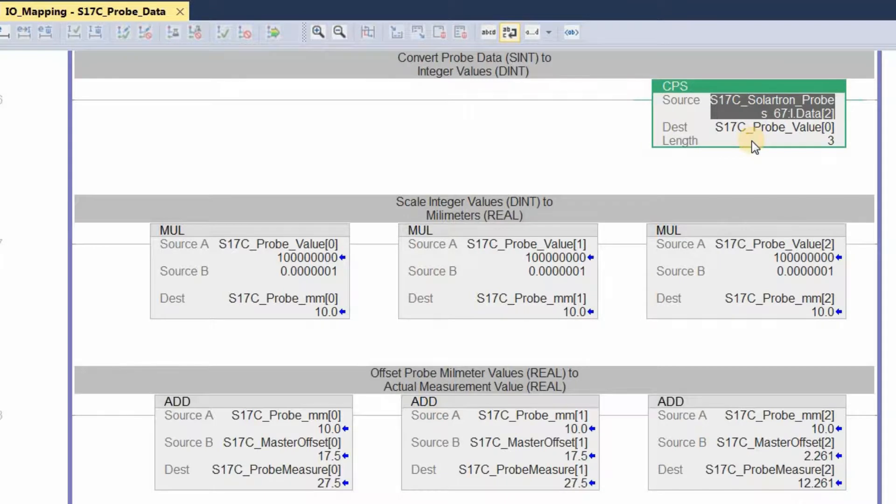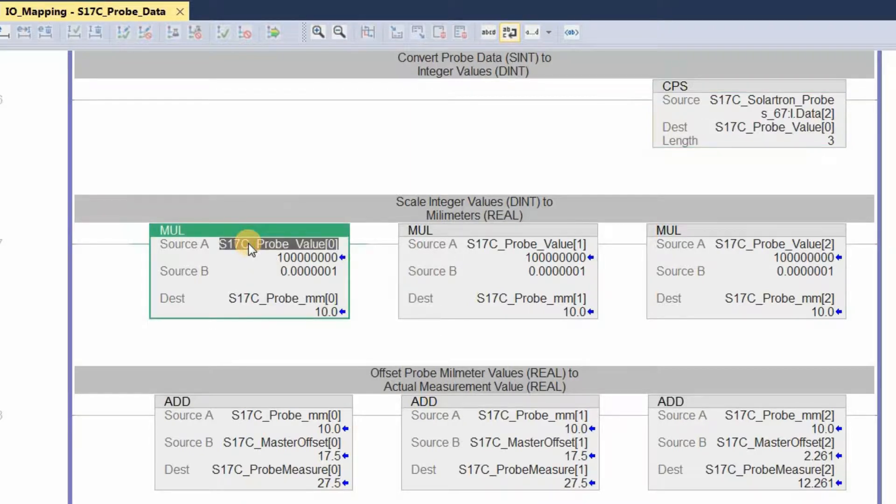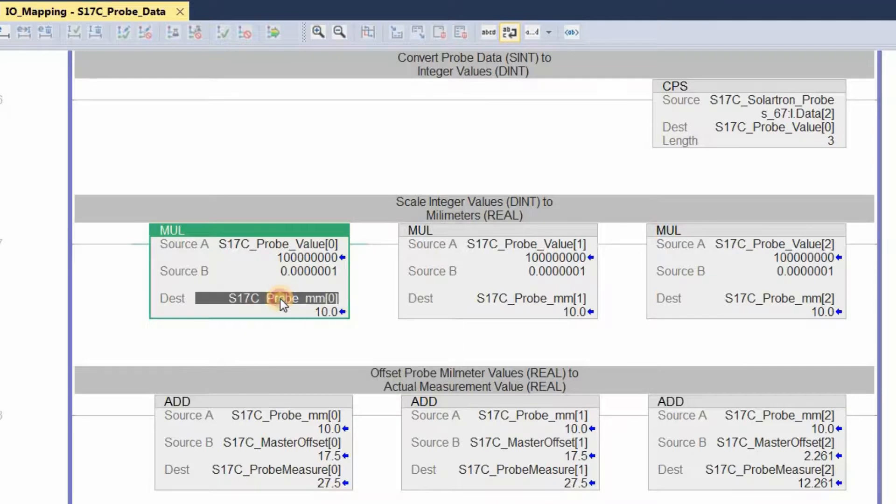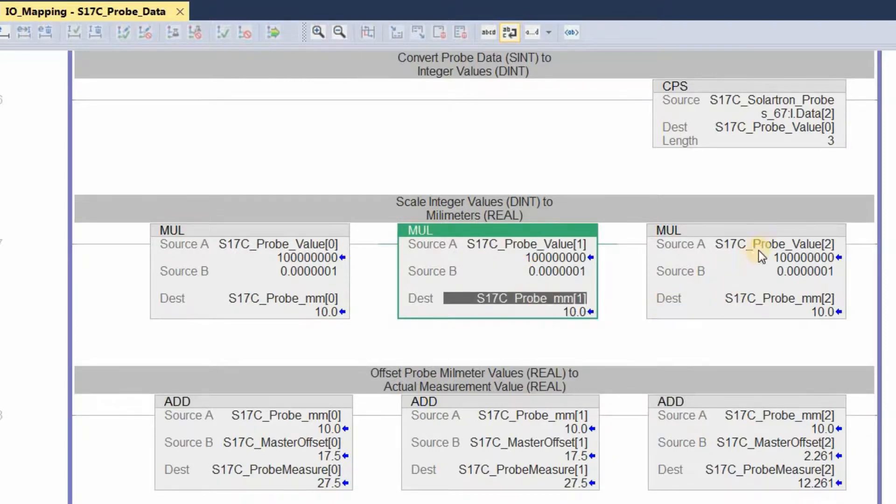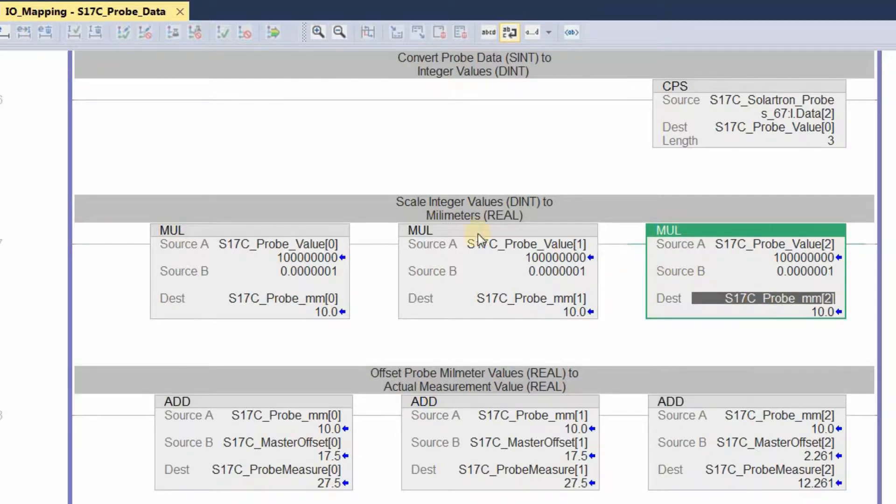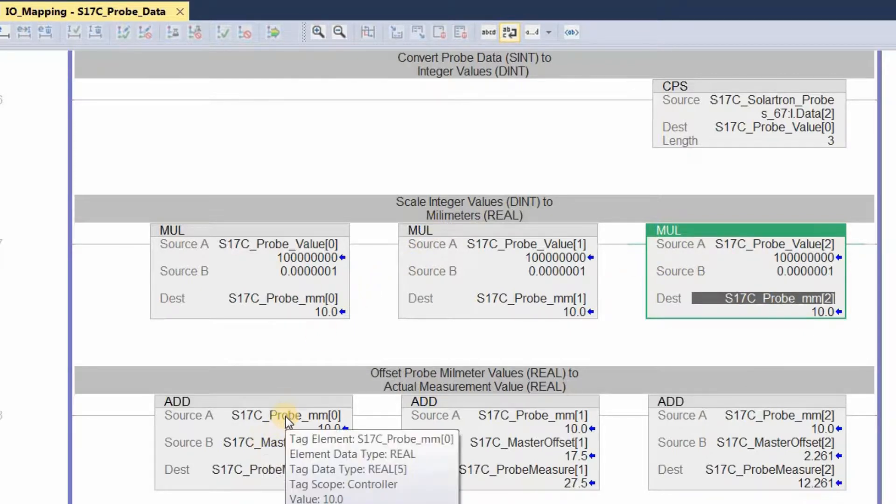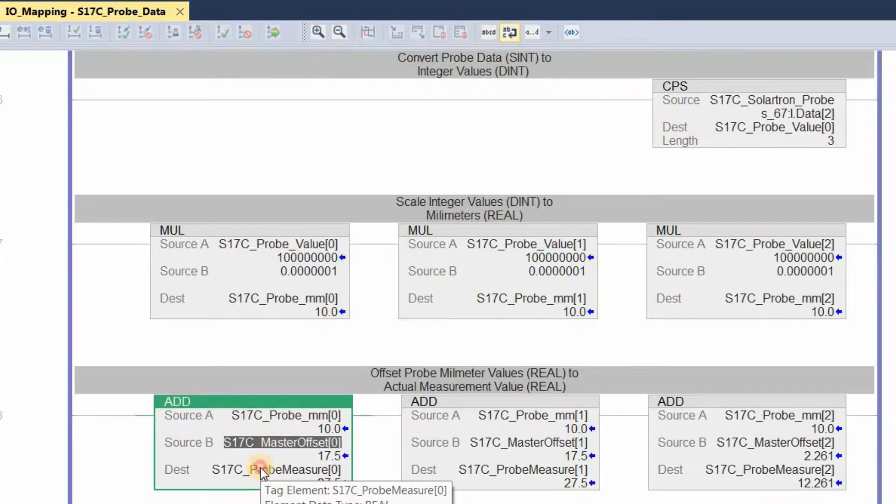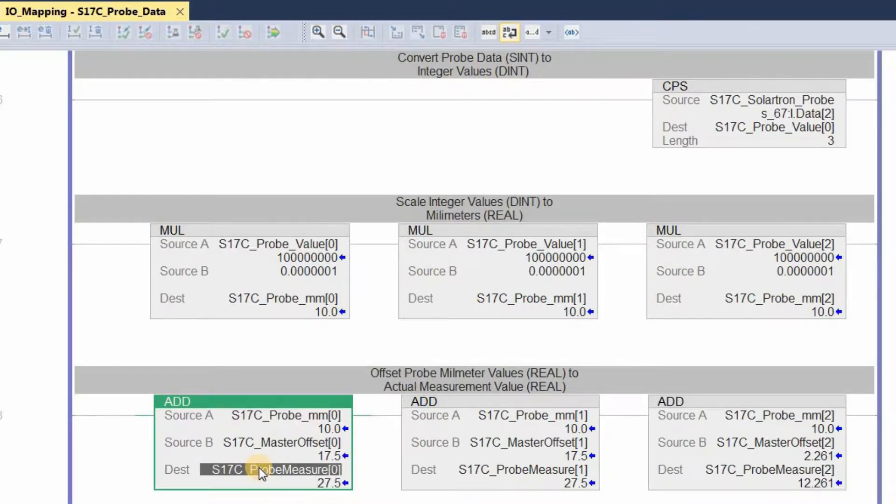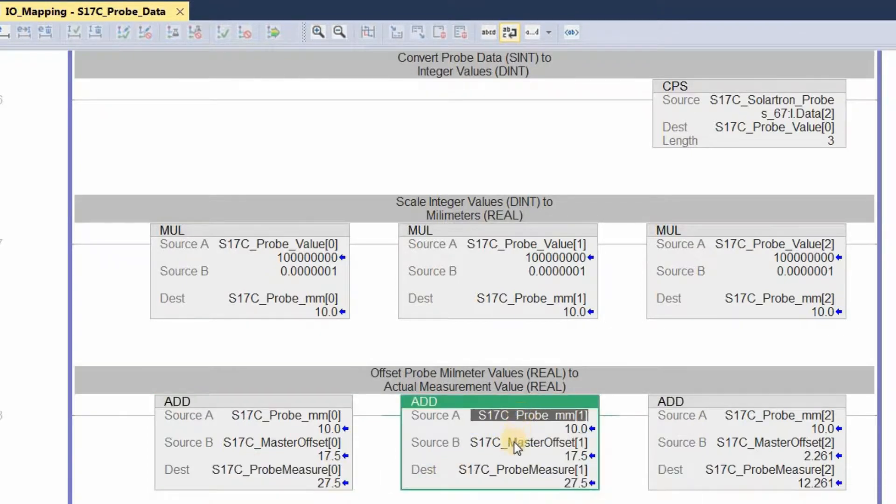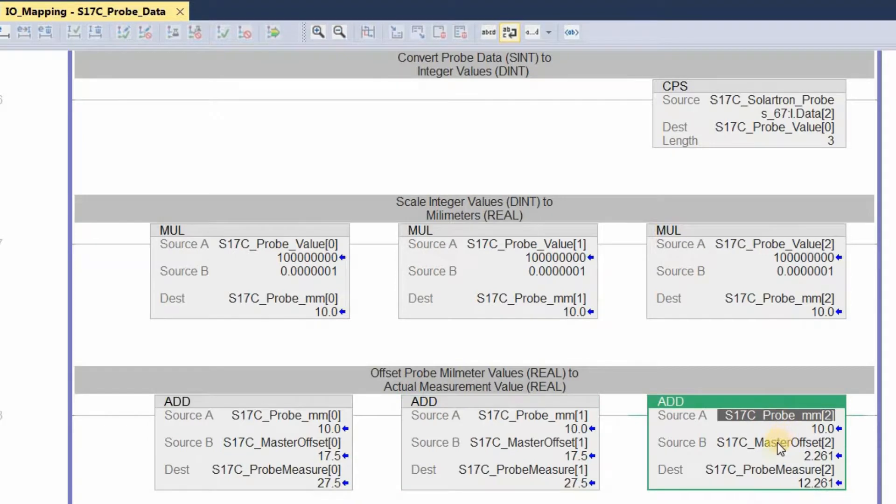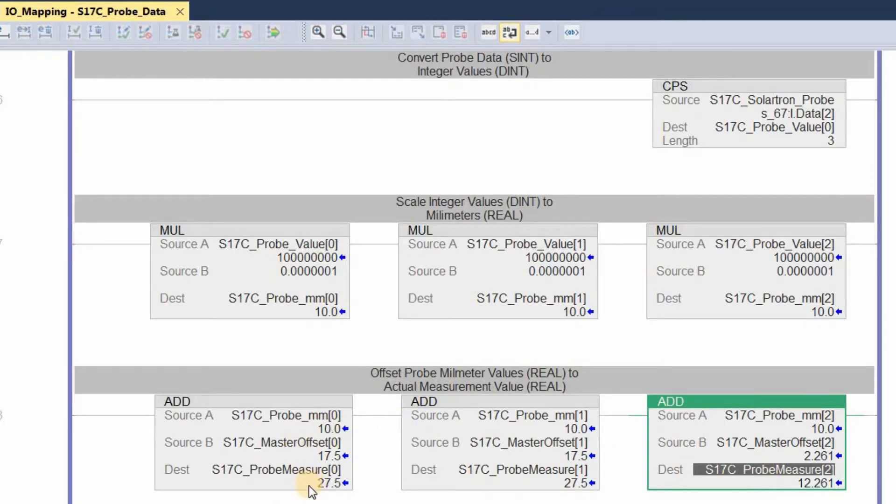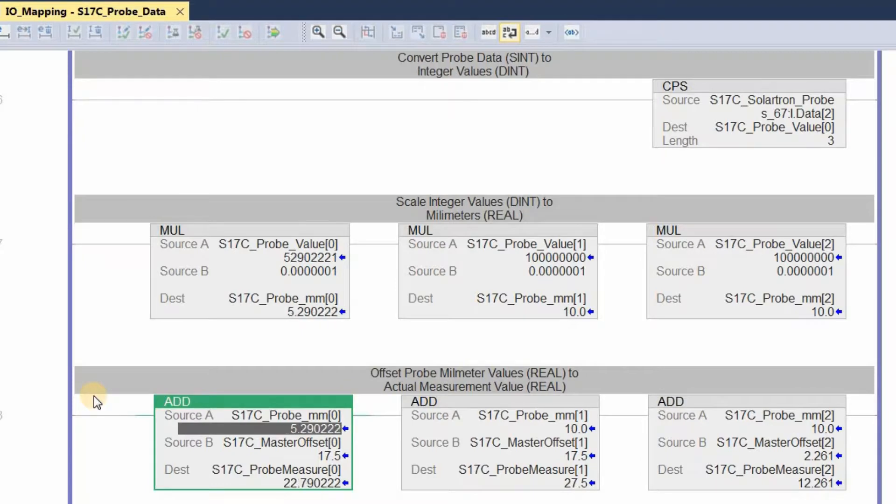Now here's an exercise just with IOMapping for taking readings from the probe. If you'll notice on the upper right hand side, you have the source, as well as the destination, and then you have three probes set up. Here's a 10 millimeter probe, and then the destination has a designation of zero. Then the second probe has a destination with a designation of one. Then the third has a destination or designation of two. Then the third row down here is actually offset values. So let's say you don't want to take the raw readings from the probe, like zero to 10, but actually have an offset value. Like for example, here an offset value is entered of 17.5 for both the first probe and the second probe. Then the third probe has an offset of 2.26. So now individual readings are being taken from each particular probe, including the offset values.